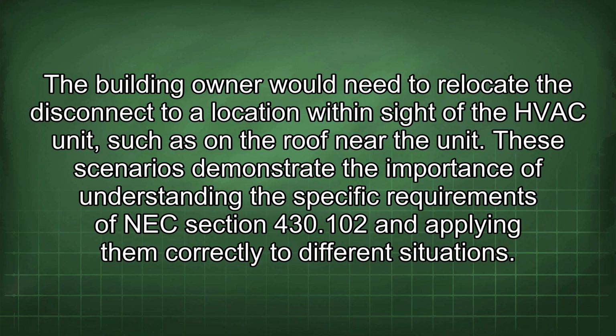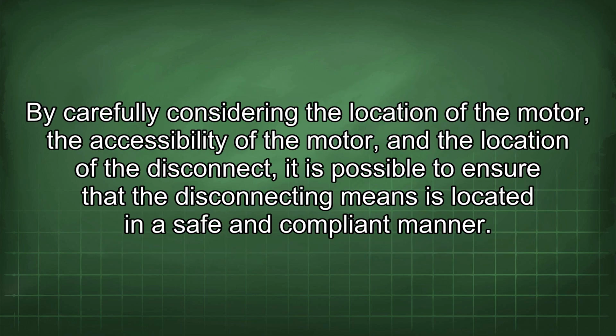These scenarios demonstrate the importance of understanding the specific requirements of NEC Section 430.102 and applying them correctly to different situations. By carefully considering the location of the motor, the accessibility of the motor, and the location of the disconnect, it is possible to ensure that the disconnecting means is located in a safe and compliant manner.